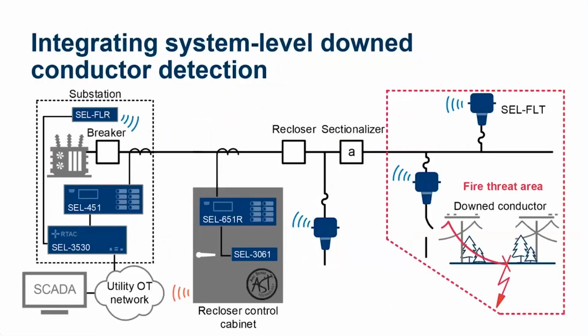Now, we can combine all of this into an integrated system for detecting down conductors. There's a lot going on in this slide, but we don't have to implement this all at once. The nice thing about building a system is that it has discrete building blocks, and we can build this out as we go. I've worked with many utilities that have just started off piloting AST, maybe on one circuit in the substation or at a few recloser controls, and that's a perfectly good place to start. One recommendation is, of course, that we're going to want communications, and we'll talk about that a little bit more when we get into applications and settings for AST. But we can combine all of this together, and the more communications we have between devices and the more we can tie all this together, the better the decisions we can make and the more visibility we're going to have into what's going on in the power system.